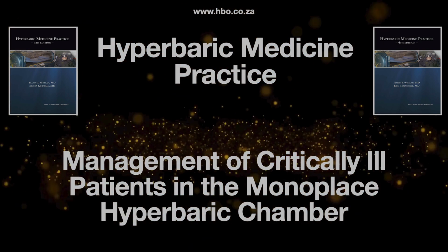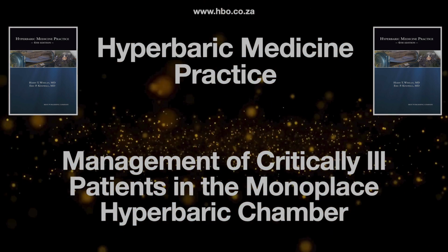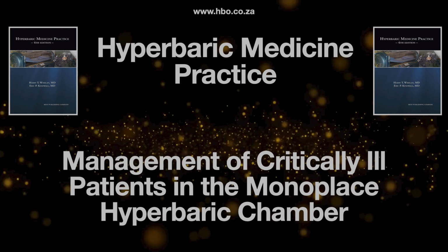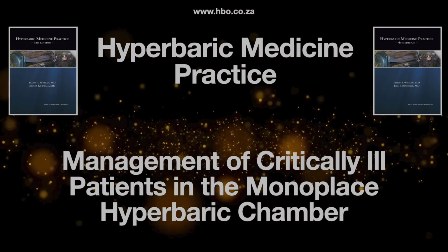You mentioned older chambers might have limited IV ports. Yeah, a real challenge. Multi-line pass-throughs were developed as a workaround, following ASME PVHO safety rules for modifying the chamber hatch. Newer chambers usually have more ports built in.